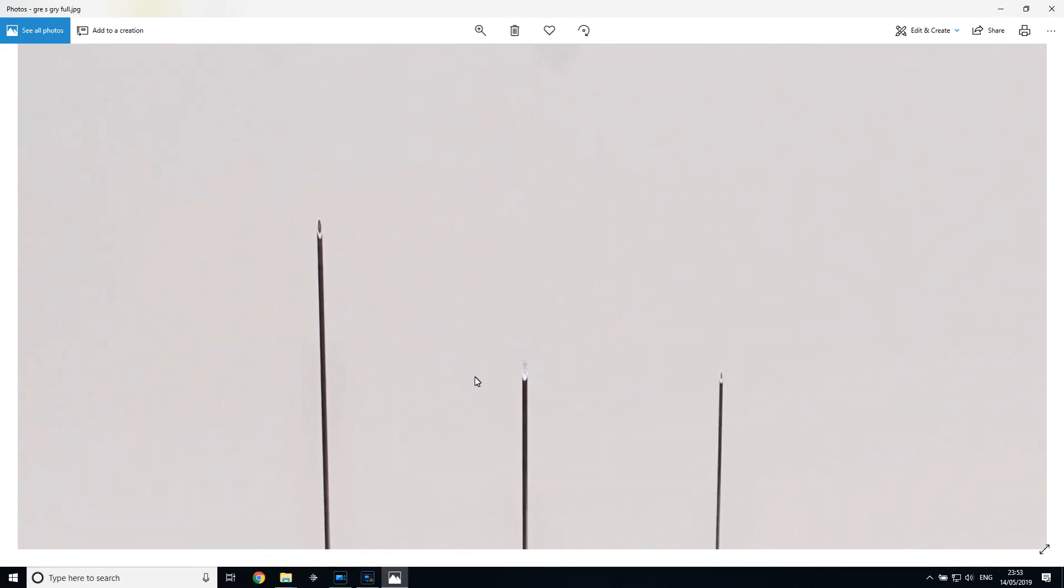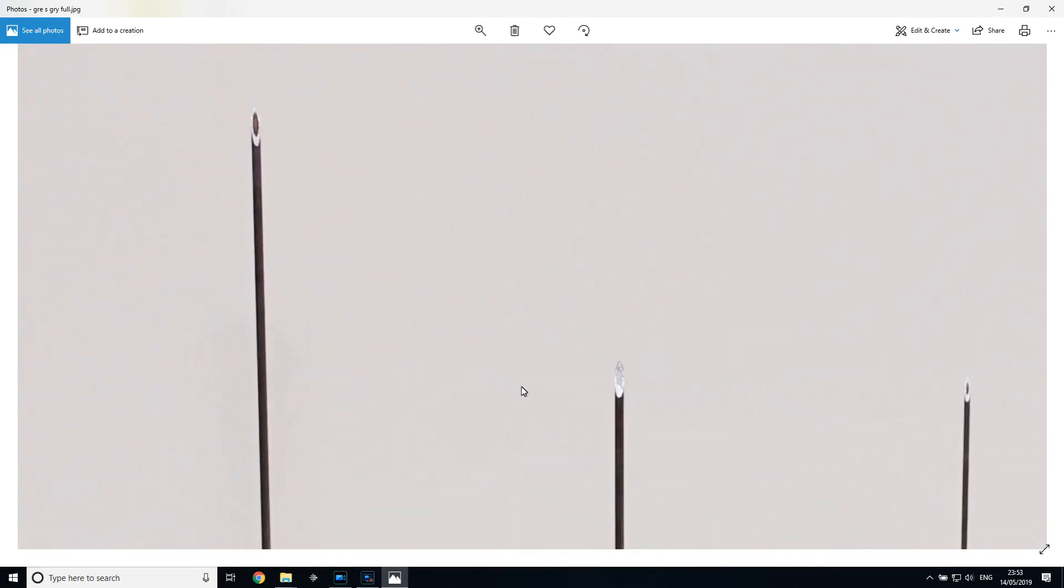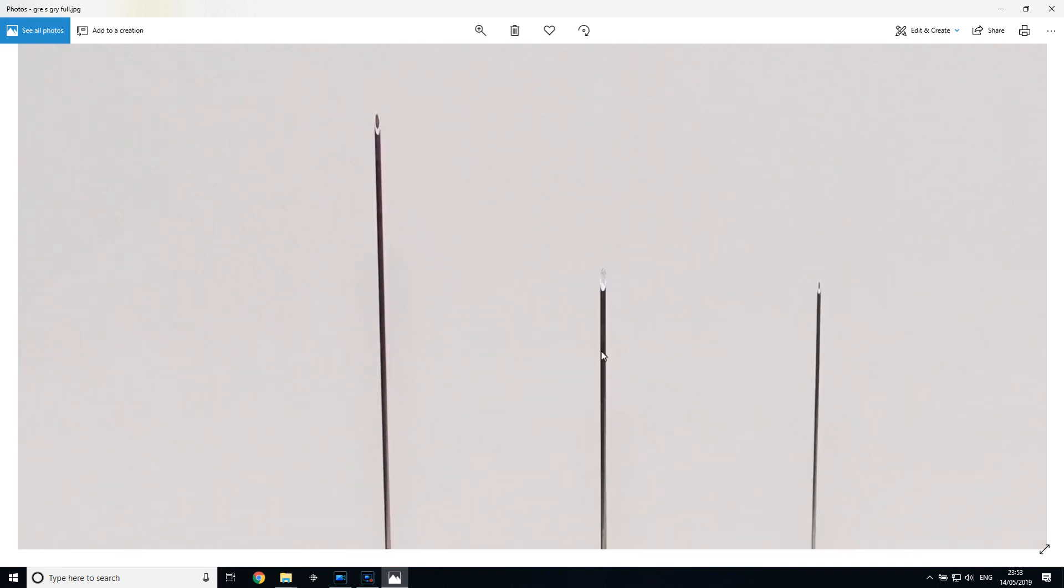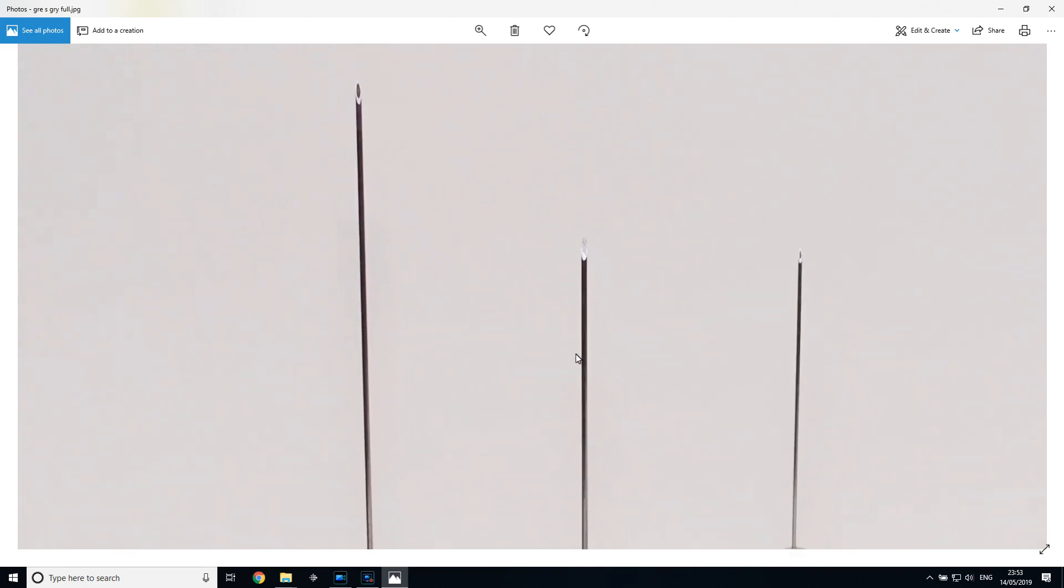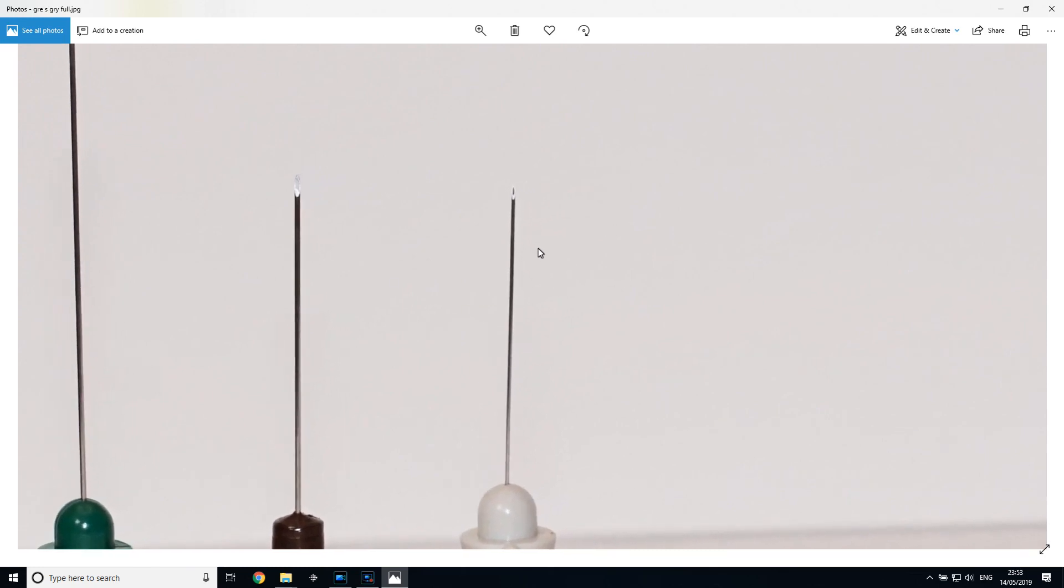The shape of the tip at the bevel is broadly the same as well, no real difference in terms of its shape between the two. You'll note of course for the concentric one, the inner core over there, whereas for the true single fiber EMG needle, you can just see this white material there which is the insulating resin. We'll come to the actual shaft of this in a bit more detail a bit later on.